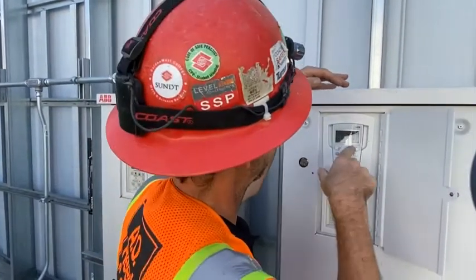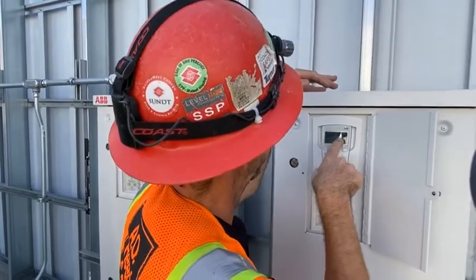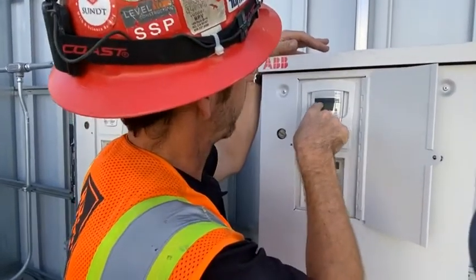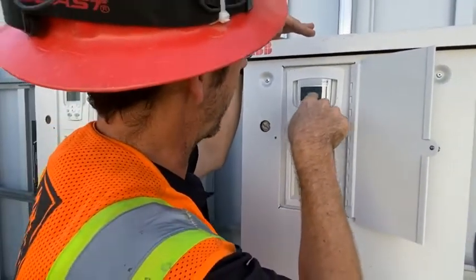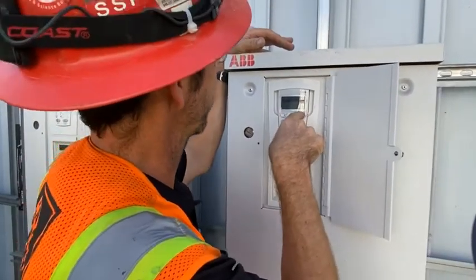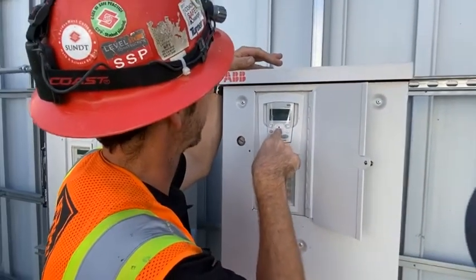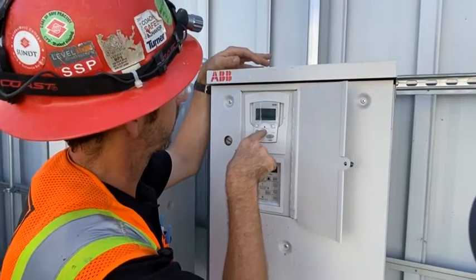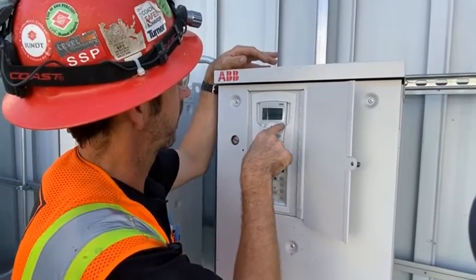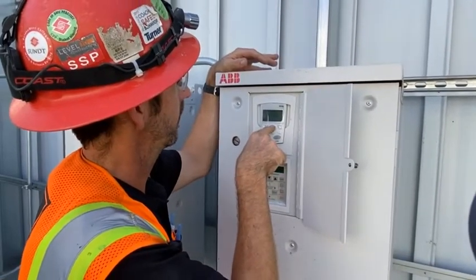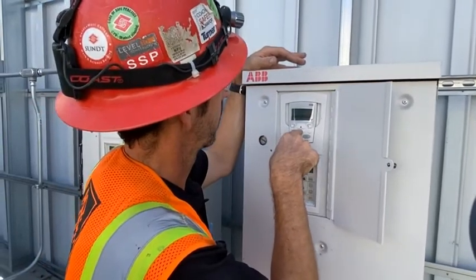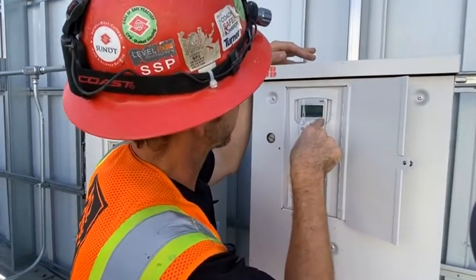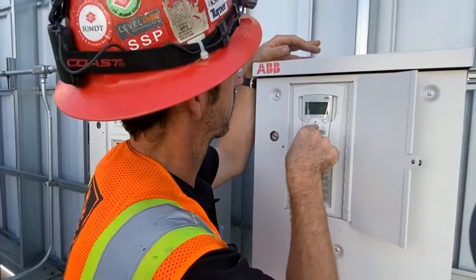So we're gonna start over. We're gonna go into panel display. Now, signal 1 is the parameter, it's output frequency. So it still is an output frequency, we just wanna change the reading to hertz from percent speed. So we go to direct on 3404. And then instead of output unit is percent speed, we're gonna go to hertz.